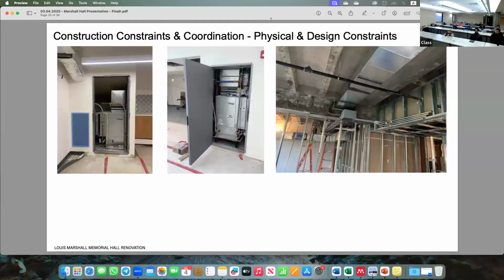Trying to fit these - there are about 86 of these units throughout the building, about 3/4 vertical and the other quarter horizontal. It took a lot of time to make sure the closets that were built actually fit them. They need to be serviced, they all have their own filters and valves, they need maintenance, and they have isolators that go under them. Making sure these closets could fit these units was something we struggled with a lot, and we had to adjust some of their locations.